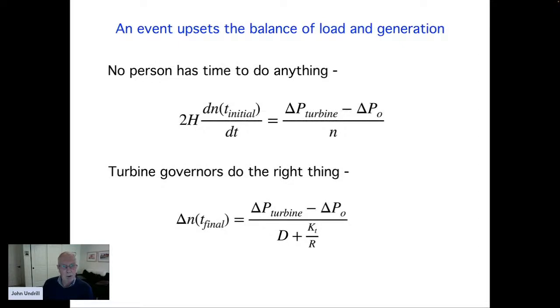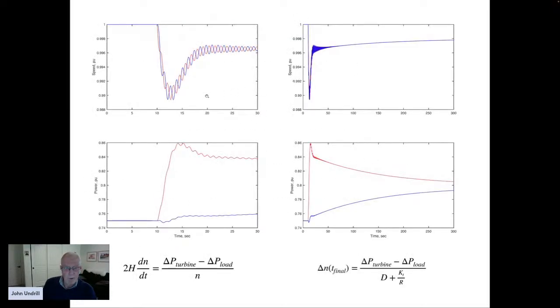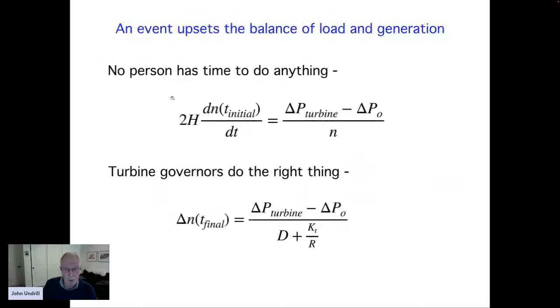Here's what happens. The frequency is going to go down in accordance with the Newtonian dynamics, but it does so in a few seconds. I'll go back one slide. From the moment that an event occurs until the event is all over is 20 seconds. From the moment that the event occurs until the frequency reaches a minimum is, in this case, perhaps 3 seconds. In 3 seconds, the guy in the control room can't do anything. He's not even looking at his screen, perhaps, at the time that the event occurs. And by the time he turns around in his chair and reaches out with his mouse to see what's going on, the event's all over. So the system responded to the event without any action from the control room. Speed changed according to Newtonian rule.